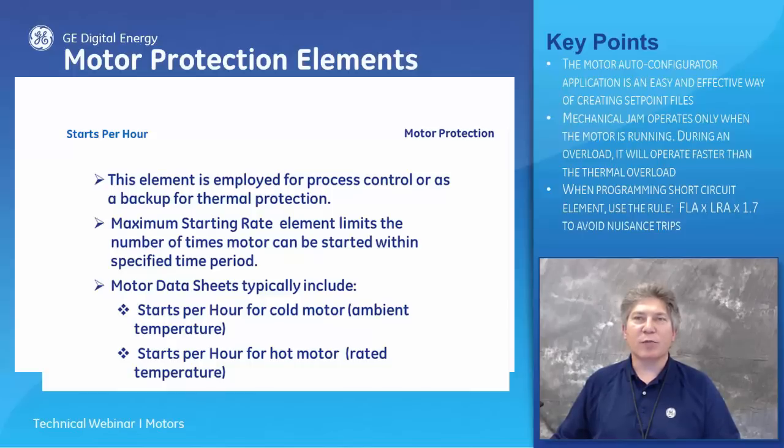The element is applied to inhibit the motor start command. If we try to start the motor more times than the setting, a lockout time is initiated until a starts per hour timer resets to zero. Note, an emergency restart clears the lockout time to 0 minutes and resets the pickup and operate operands.